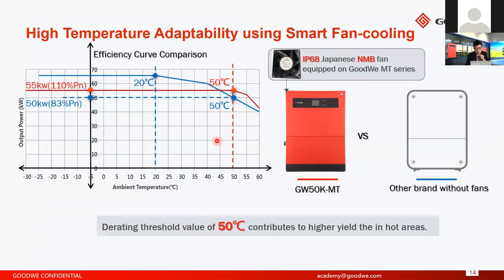And here is our main feature, compared to another brand. So you can find here, our inverter will start derating from 50 degrees. So if the temperature is lower than 50 degrees, the GoodWe inverter will output normally without derating. But if you use another brand without fans, no fans inside, the inverter will start derating. You can find the blue curve.